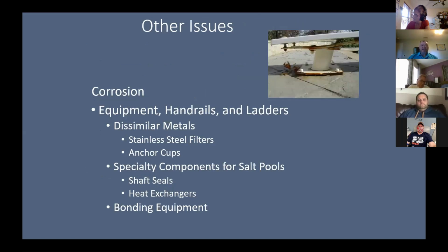Other issues that we see: corrosion, like I talked about before. One of the things with salt systems is we tend to hear that chlorine generators cause corrosion. As you can see in the picture with the standoffs for the diving board, it can cause corrosion. If you live anywhere along the ocean front, anything metallic you can see has oxidation or corrosion on it. It happens with salt systems. And the fact is, like I talked about on the slide on salt, when you get to 6,000 parts per million or higher, it will be corrosive to metal.